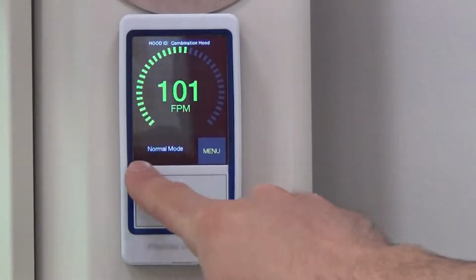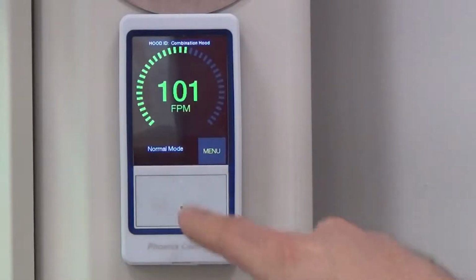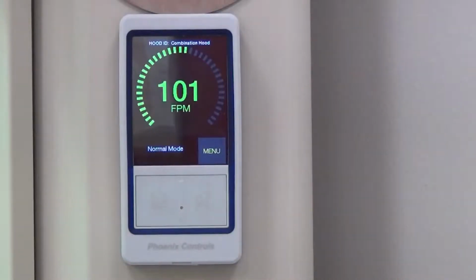This information pane down here that now says normal mode will actually give the user a lot more information than we ever gave them as well. So if I open the sash on this and this fume hood goes into setback mode, it'll actually say setback mode or normal mode. Because this is a network device, we can actually map things like outside air temperature or room temperature to the fume hood display. That information pane will also give you some alarm information as well. So in the case that I leave my sash open and walk away from my fume hood, so let me go ahead and do that.